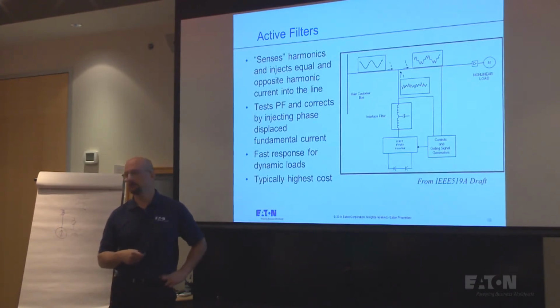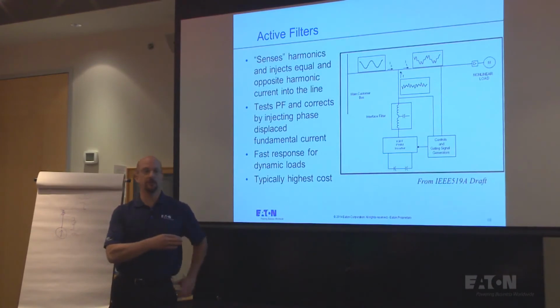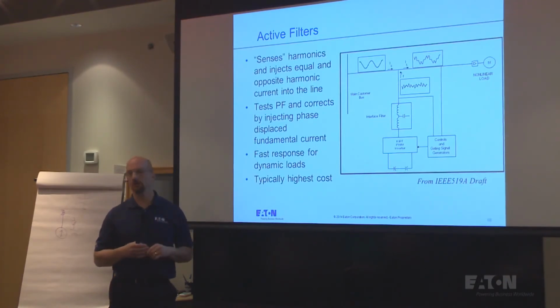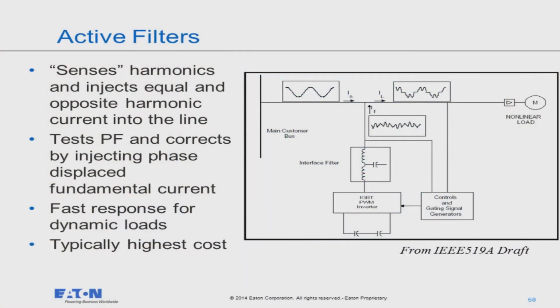People are using a lot more active filters just because it's something you can design up front that you don't need to know precisely the exact harmonics, whereas with a harmonic filter, a lot of times you need to know a little bit closer the actual harmonic current you expect and the power factor of the system that you expect so that you can do it right.